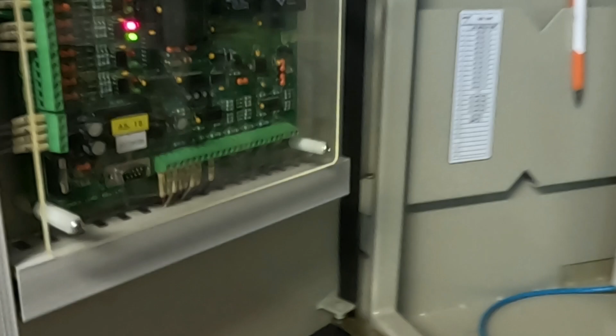At least once a month we test with span gas containing these flammable or toxic gases. Then we introduce this gas to our sensors. It can go here, or on the other side.